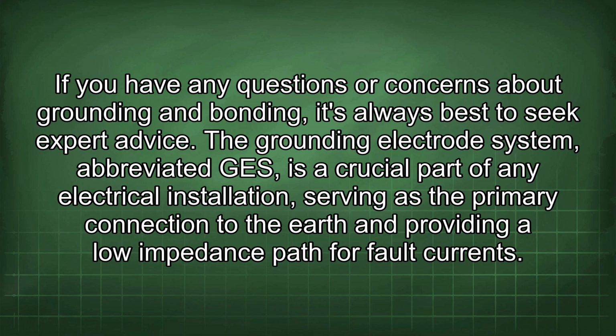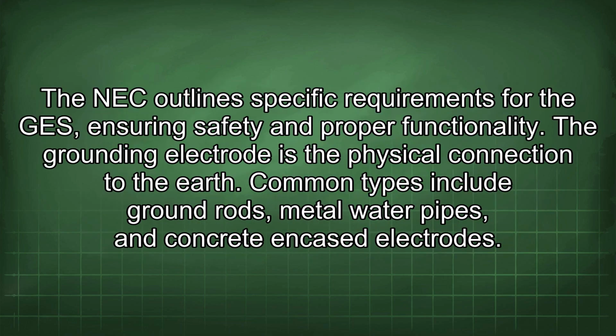The grounding electrode system, abbreviated GES, is a crucial part of any electrical installation, serving as the primary connection to the earth and providing a low impedance path for fault currents. The NEC outlines specific requirements for the GES, ensuring safety and proper functionality. The grounding electrode is the physical connection to the earth. Common types include ground rods, metal water pipes, and concrete encased electrodes.